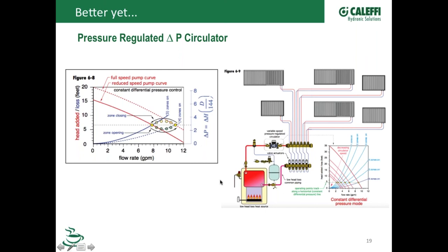There's a couple different settings on those: constant pressure, and there's an auto adapt feature. Again, we did a pumping webinar that tells you a little bit more about the different types of settings and which one you would use, or you can just use the auto adapt, and over the course of a couple days it'll actually learn this condition, what happens as these valves are closing off, and that pump will automatically adjust to exactly what you need. Think of it as a cruise control on your vehicle. If you're going down the highway and you want to just maintain 60 miles an hour all the way down the street, you just put that cruise in and it adjusts the accelerator, the amount of fuel going to the engine, and it makes your speed exactly right. That's really what we've done here, is we put a cruise control on our circulator pumps.